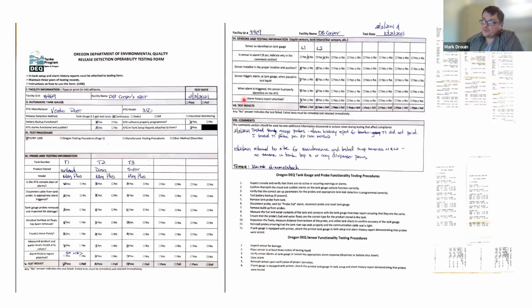We also put on the form, just like we filled out this form on site, pretty simple. We feel it's simple. This isn't a real facility. We went to a DB Cooper spot. They had 3 tanks. We tested their probes. They also had 2 tank top sensors. We tested those just to make sure everything worked. We followed the PEI guidance document. And this is the form that I would present to the inspector if I own this facility.